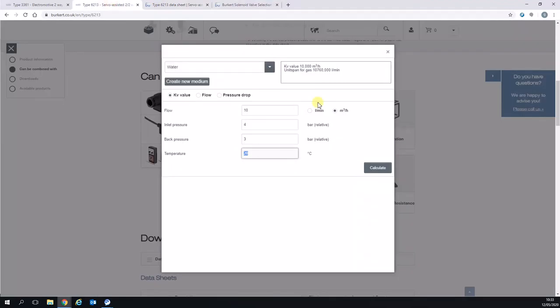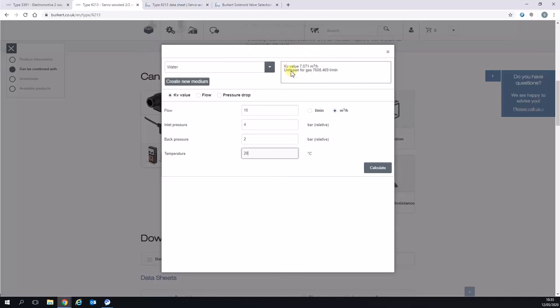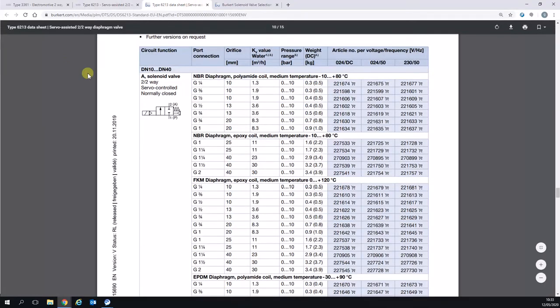What if we change those pressure drops? For example, if we double the pressure drop, so we go from four to two, you will eventually see when the system catches up that the KV now has dropped to seven. So we need to find a valve that has a KV value greater than seven to achieve the flow rate of 10 meters cubed with a two bar pressure drop.